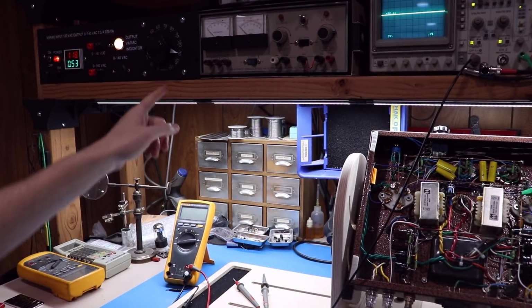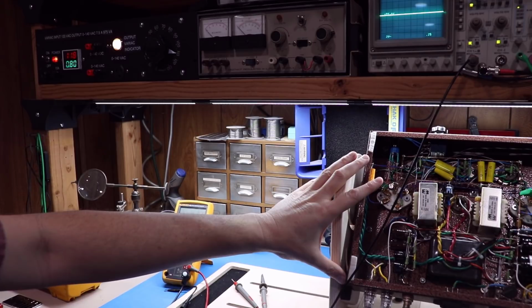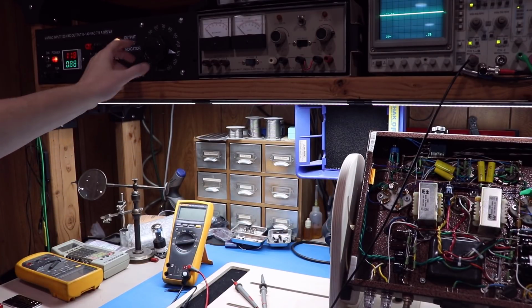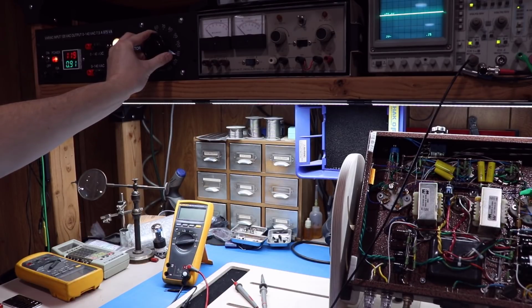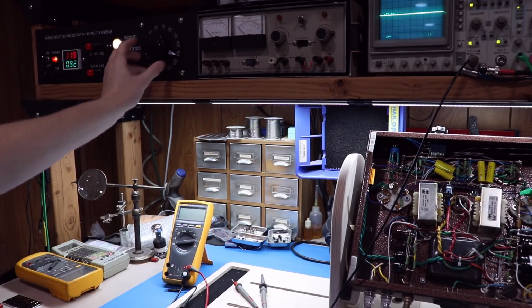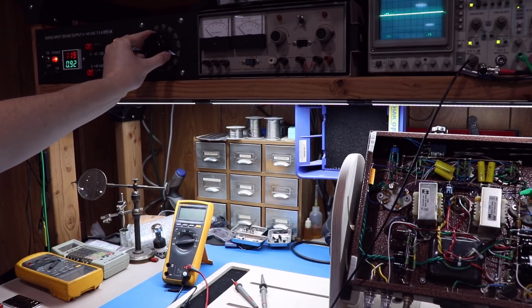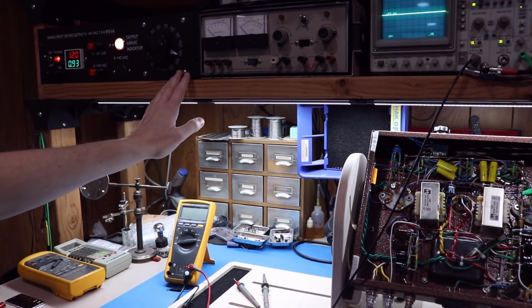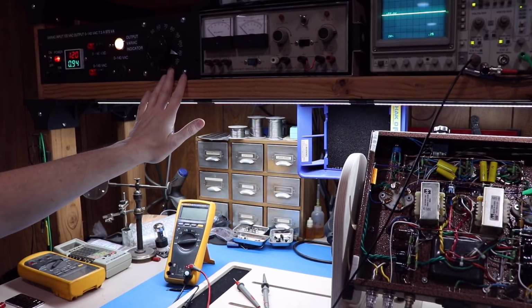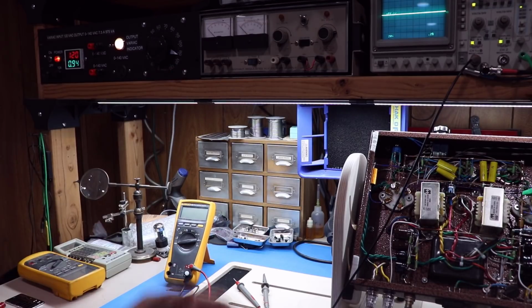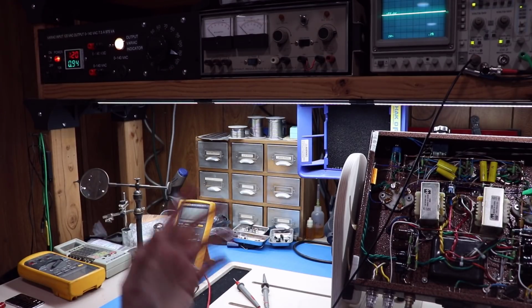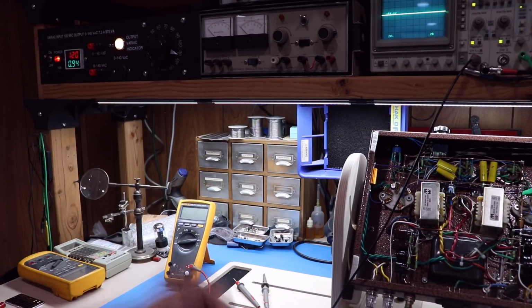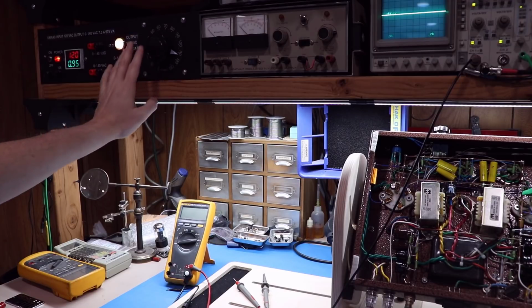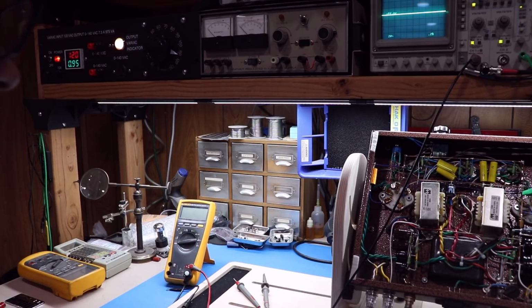Okay, one other thing you'll notice is I run everything I do on a device under test up here through a variac, and you can see I'm at 118 volts. I'll get it up to 120 volts or whatnot right here. A little touchy today. But I need you to understand, a variac is an autotransformer. It is not an isolation transformer. I run into people from time to time and they'll say, well, hey, I've got an isolation transformer in place and I'm using my variac to do that. It is not. This does not isolate ground. It doesn't isolate the neutral the way you would need for these purposes.